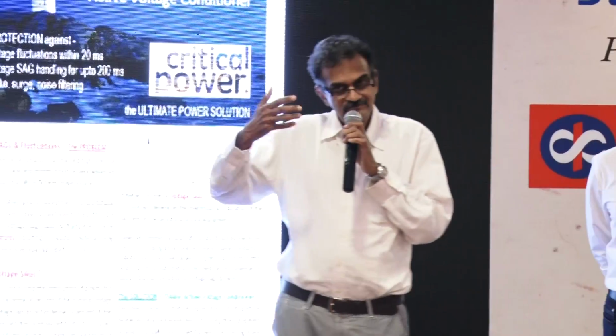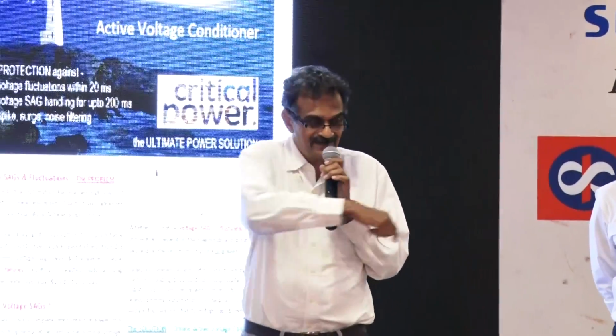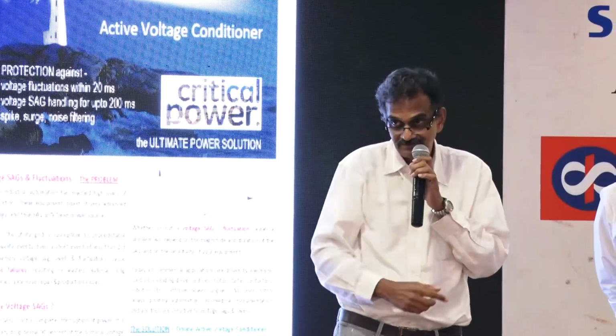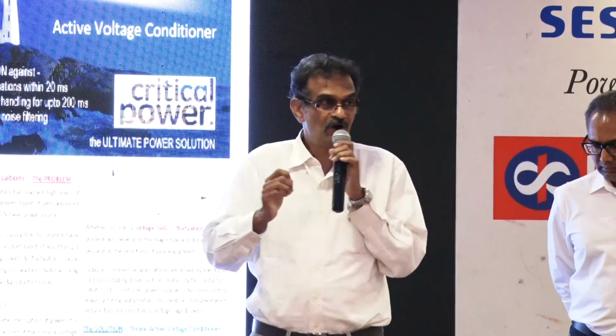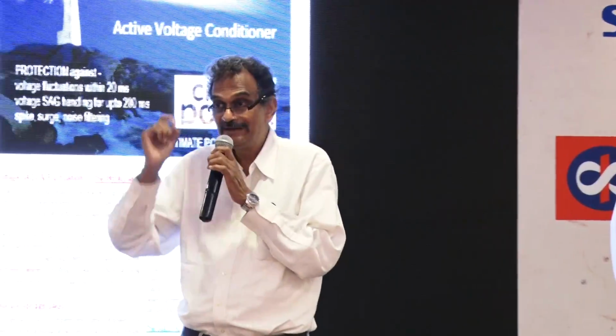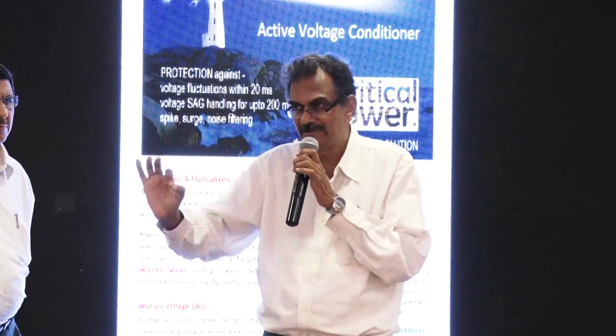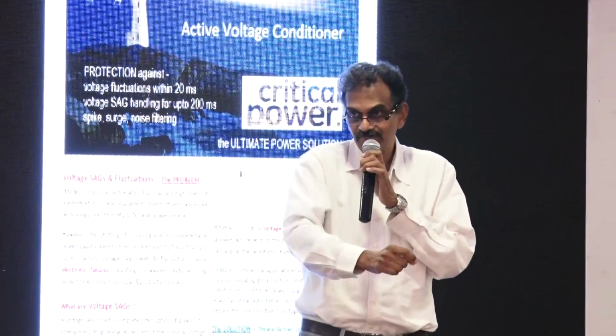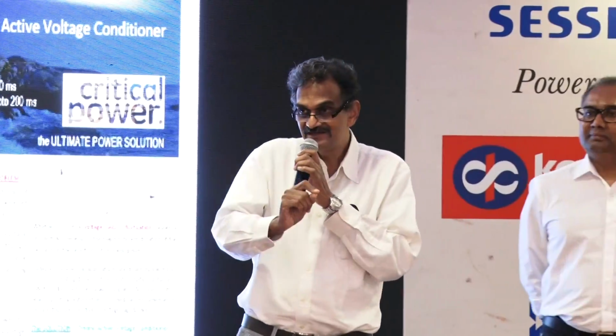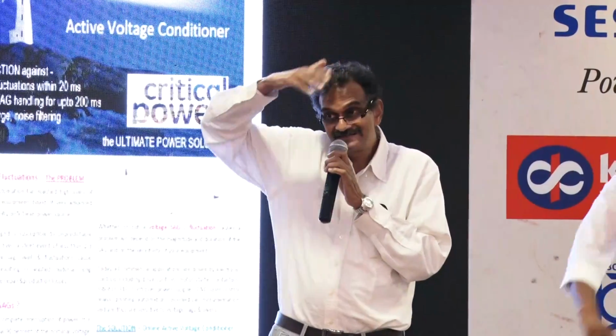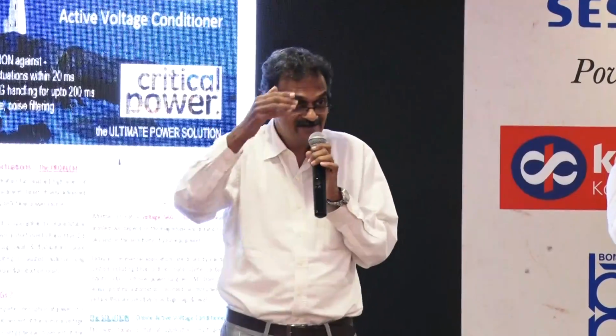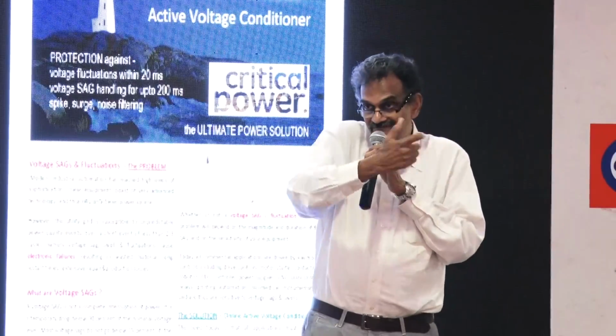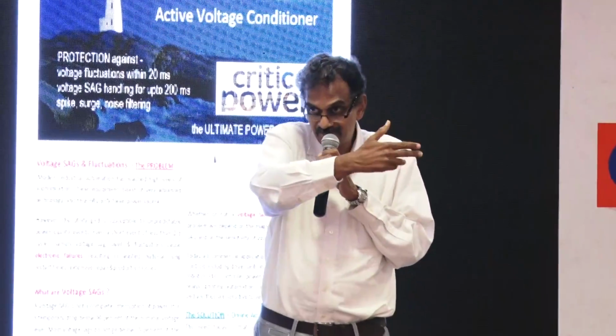We need to ask a question — is something happening within the machine, is there a fault? What I'm requesting each one of you is please maintain logs. Simply put a book and a log. That log will record when the incident occurred and what other things happened at that time. If you start maintaining a log, these problems can be caught out. There's a possibility that sometimes a drive is going bad or there's a fault. So when does a fuse blow?